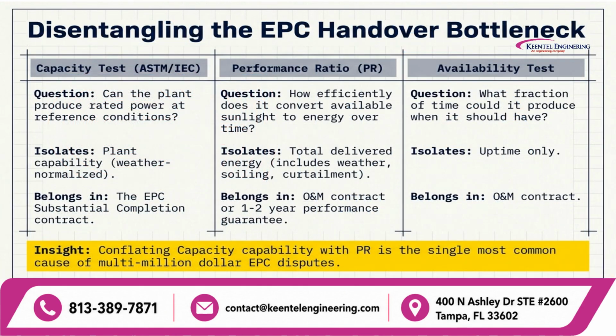A major driver of multi-million-dollar handover disputes is the conflation of contractual testing regimes. Capacity testing evaluates whether the physical plant can generate nameplate power under normalized reference conditions and belongs strictly in the EPC substantial completion scope. Performance ratio measures multivariable system efficiency over time, including external environmental factors, and belongs in the long-term O&M agreement. Availability testing isolates operational uptime alone. Mixing capacity with PR during handover creates unnecessary gridlock and legal exposure.